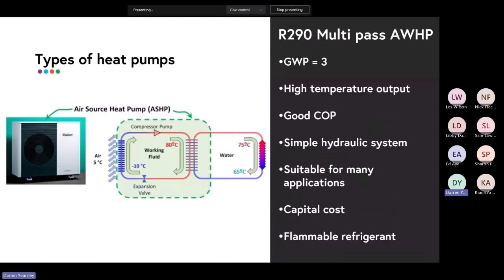Okay, so if we compare that to an R290 system, an R290 is much more like an R410A or an R32. It's what we call multi-pass. So a multi-pass appliance is not looking for a 50-degree difference. It's looking for a 5 or 10-degree difference. So it works much more like a boiler, where you can have 50-degree water returning to the heat pump. It'll heat it up by 5 degrees, put it back into the cylinder. Now you'll have 55-degree returning. It'll heat it up to 60. Now you'll have 60 returning. They'll heat it up to 70.